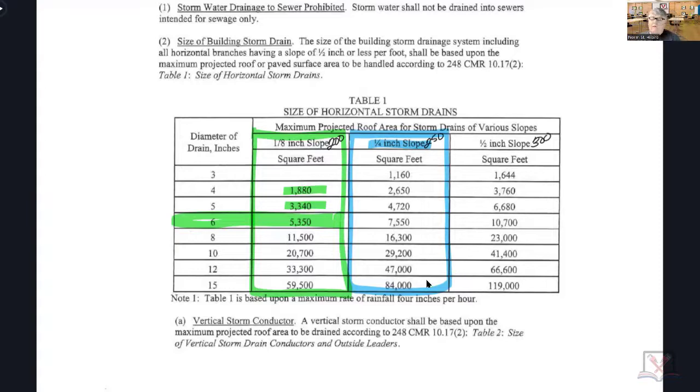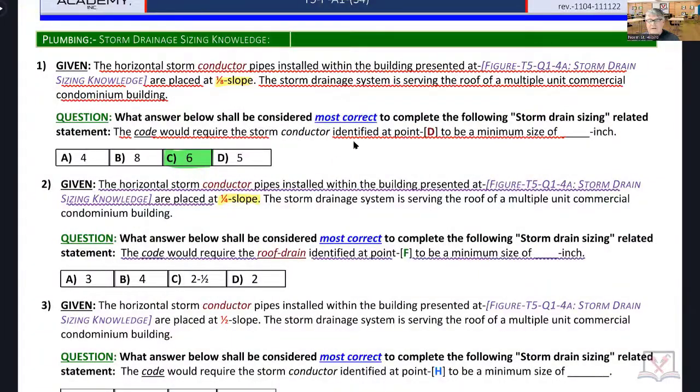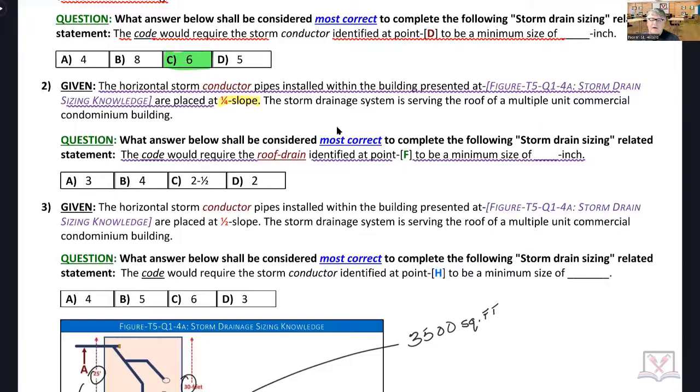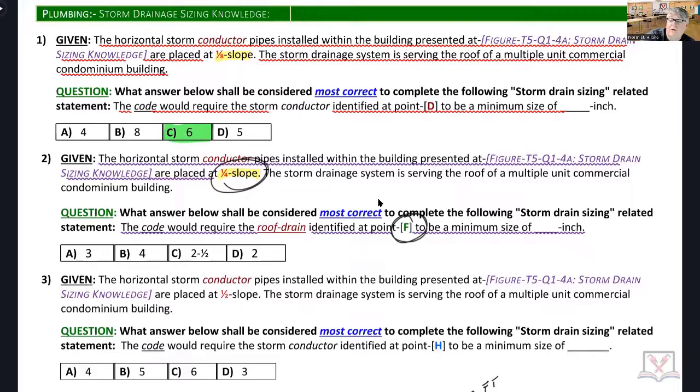Was the slope important? Did the slope mean anything to you in question two? The slope meant nothing, but it was there. It had nothing to do with sizing pipe F in this question because pipe F was pointing directly at the circle, which represents the roof drain. The water is going to go down the roof drain vertical before it goes horizontal. It was just a distractor, pushing some of you into table one when you truly needed to be in table two.